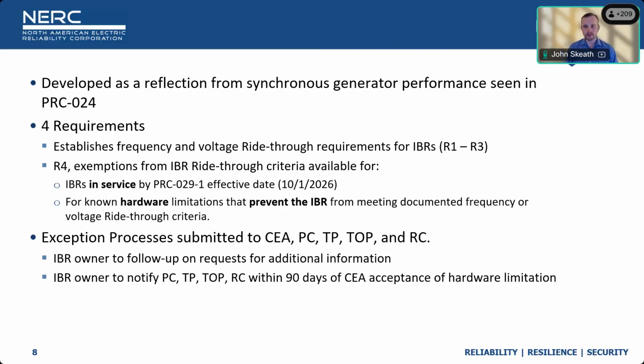There are 4 requirements in PRC-029. Requirements 1 to 3 establish the frequency and voltage ride-through requirements, graphs, charts, etc. for the inverter-based resources. Requirement 4 is the exemption process, and that is how we're going to treat the requirements expected of seeking an exemption from R1 through R3. So R4 applies to IBRs in service by PRC-029-1's effective date, 10/1/26, and it's for known hardware limitations that prevent the IBR from meeting documented frequency or voltage ride-through criteria. That process needs to be submitted to your compliance enforcement authority, planning coordinator, TP, TOP, and RC. So I realize I need to probably spell out the transmission planner, transmission operator, and reliability coordinator.